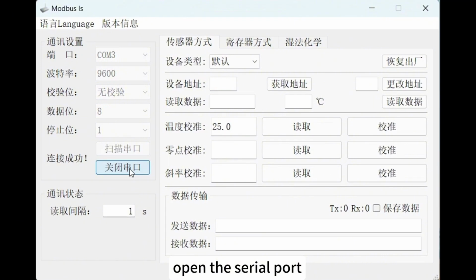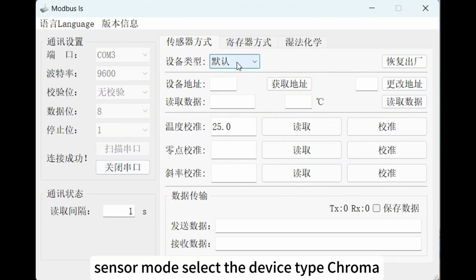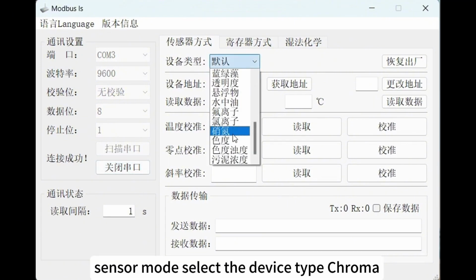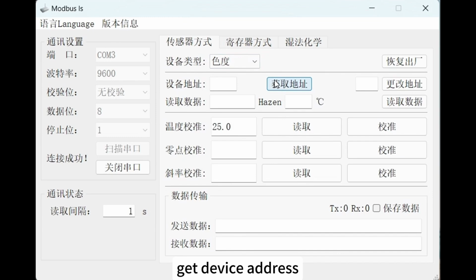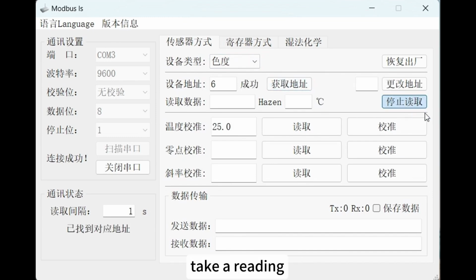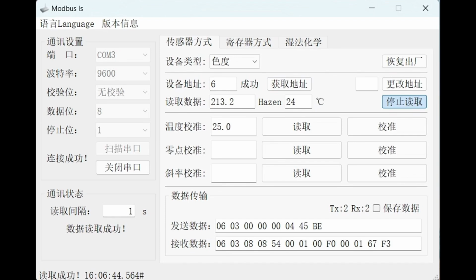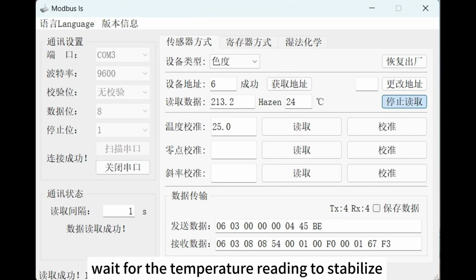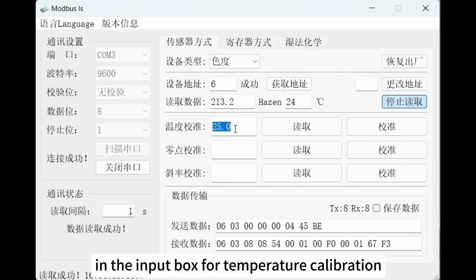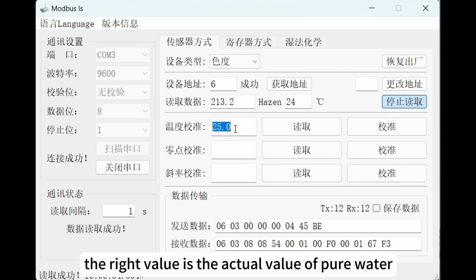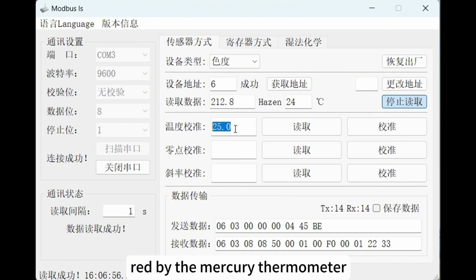Open the serial port. Sensor mode. Select the device type. Chroma. Get device address. Take a reading. Wait for the temperature reading to stabilize. Enter the right value in the input box for temperature calibration. The right value is the actual value of pure water read by the mercury thermometer.